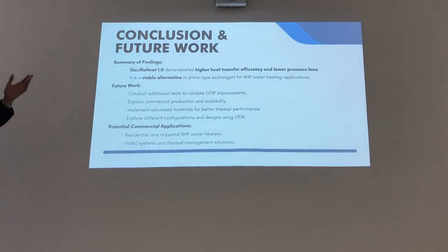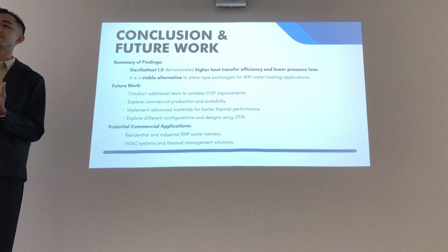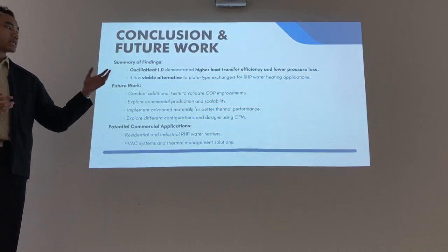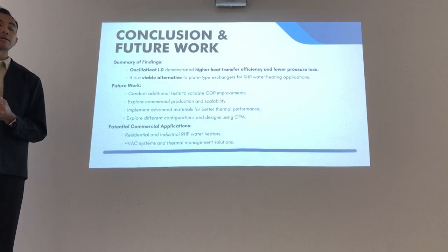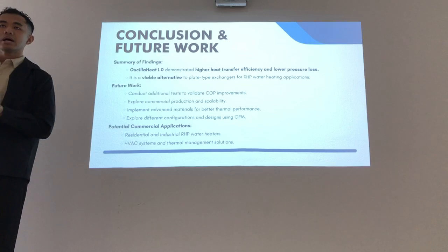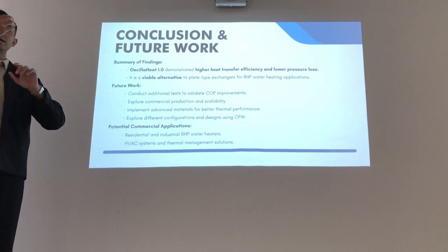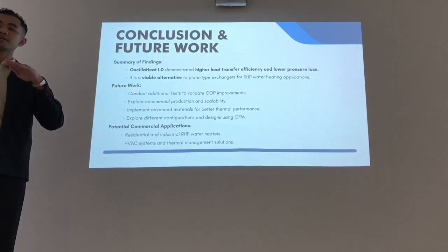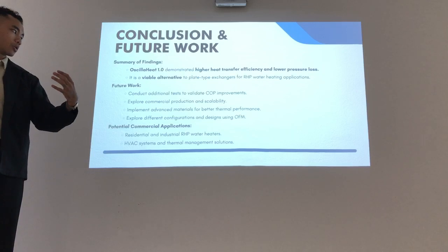So the conclusion of my work is that OscillaHeat 1.0 demonstrated a higher efficiency compared to the brazed plate type heat exchanger. It's a viable alternative as a heat exchanger on its own for RHP water heating applications. For future work, I would like to put it into a system and test the COP directly, so we can see the difference between the plate type and my own OscillaHeat 1.0.